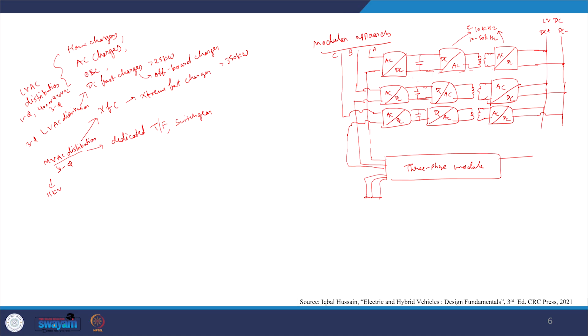So with this particular approach, for the A phase, if you look very carefully, you have this converter, and then you have this different three phase module. There are so many modules like this, there could be several modules, connected in series, and this will go from the A phase terminal and neutral terminal, and this again will go and connect to the DC bus.